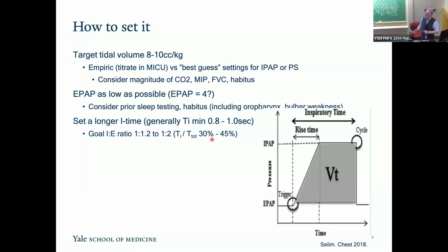In general, we want an inspiratory to expiratory ratio of between about 1:1 to 1:2. Some of the ventilators report TI over T-tot, and these ratios, 1:2 and 1:1, reflect a TI over T-tot of 30% to 45%, rather. You want to set high sensitivity and low cycle. You want to make it easy for the patient to trigger the vent, and you want to make it easy for them to continue the breath until the flow finally cycles off and the breath is released.